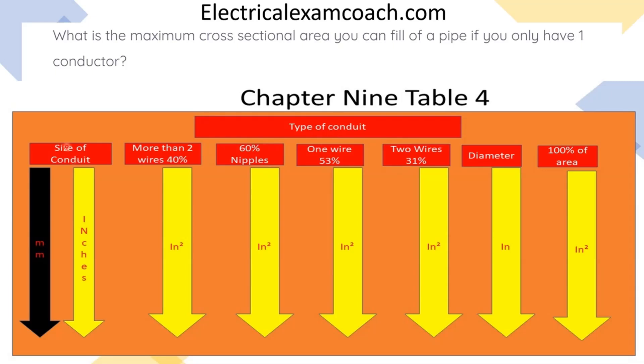On the left-hand side of this table is our size conduit. If we have more than two wires, if we have a nipple at 60% or any other 60% value, and then if you're only doing one wire, and where this would be practical is like if you're doing a grounding electrode conductor or something like that, but you're only allowed to fill that pipe 53%.